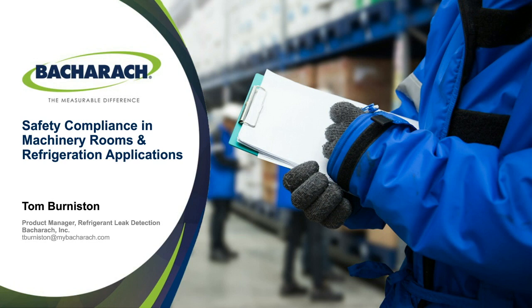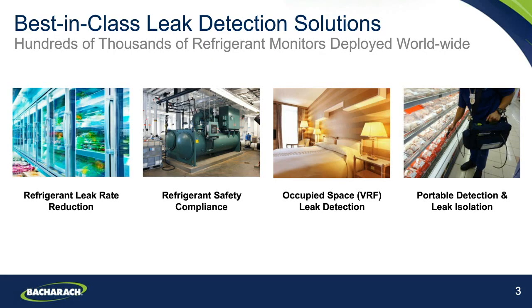For those of you who may not be familiar with Bacharach, we are a global leader in the design and manufacture of precision gas detection instruments. We make refrigerant monitors for a variety of applications, including refrigerant leak rate reduction, think supermarkets or other high-volume refrigerant users, refrigerant leak detection in occupied spaces, specifically occupied spaces that are using a VRF system to condition the space, and of course, refrigerant safety compliance in machinery rooms, which we will be discussing today.